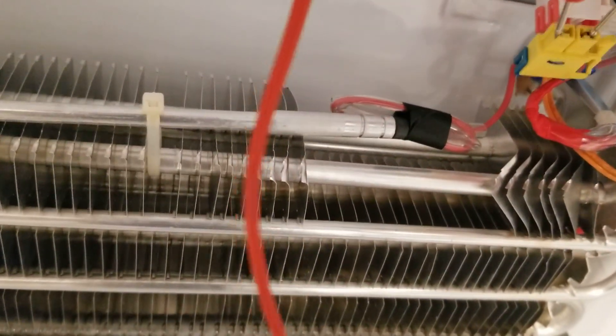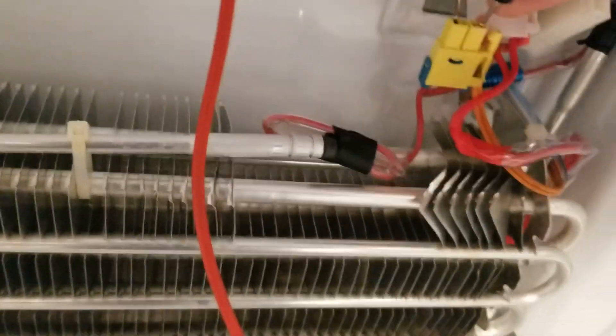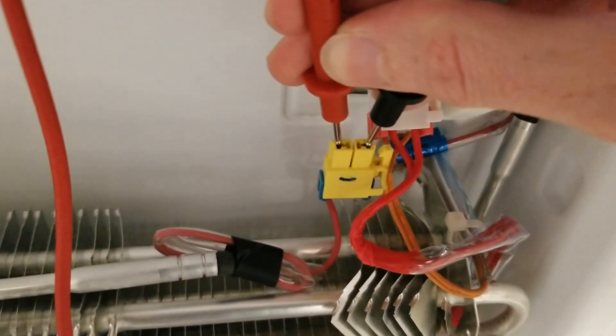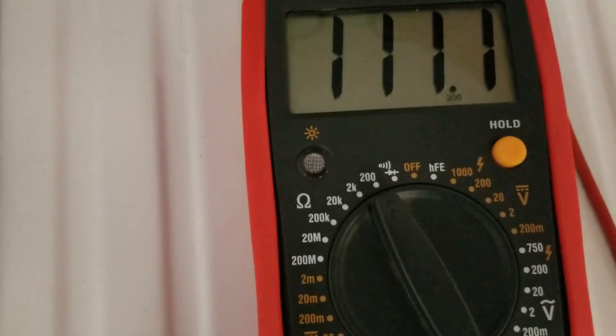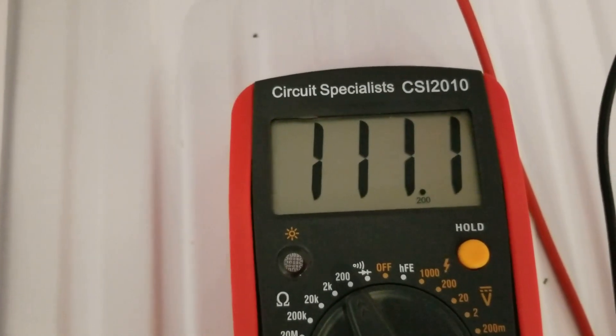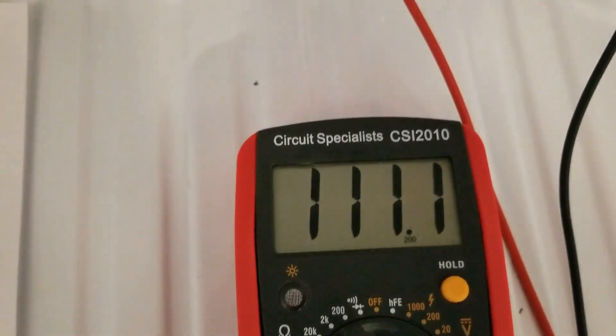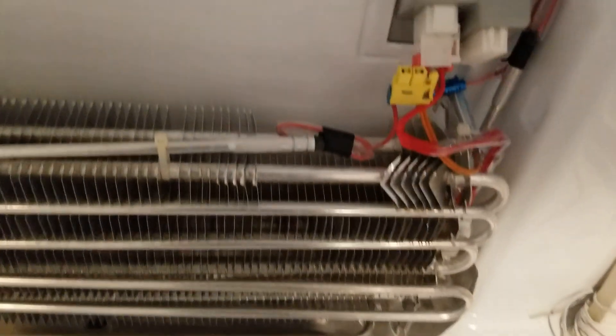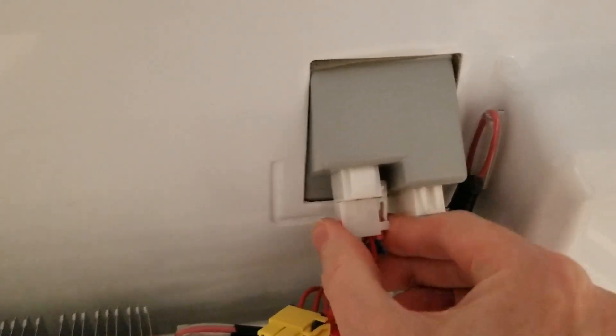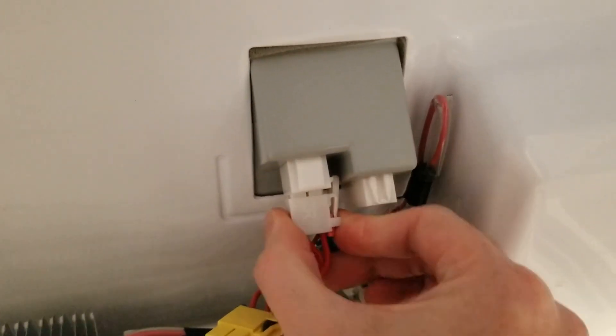Trying to do this one-handed, so excuse me. It doesn't matter which polarity is which, this is just resistance. As you can see, I'm showing about 111 ohms, so the heater seems fine.